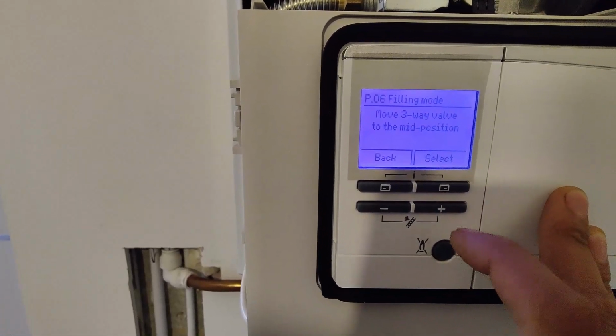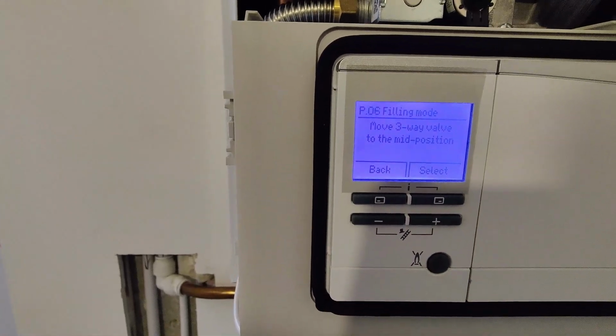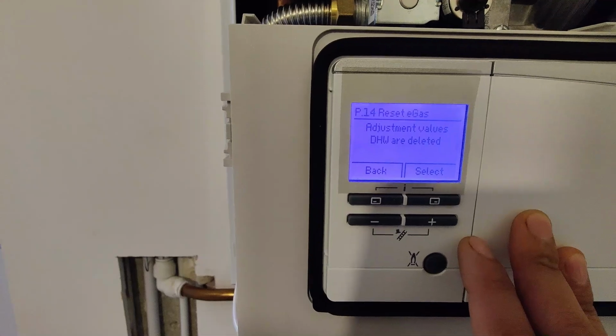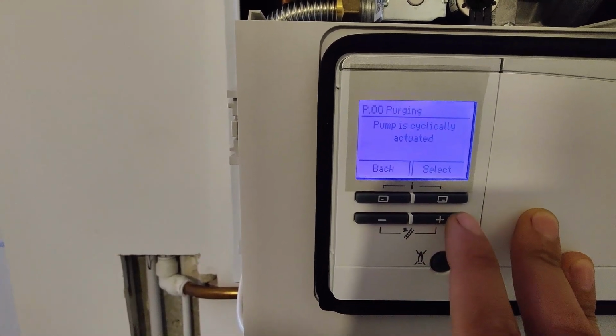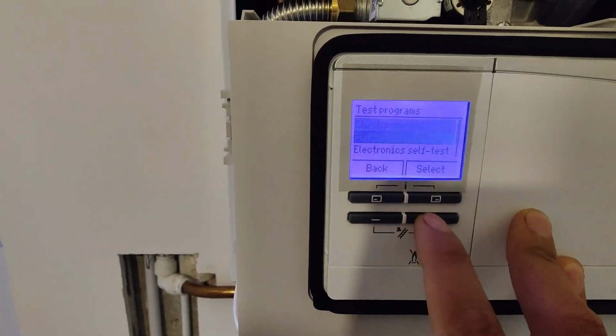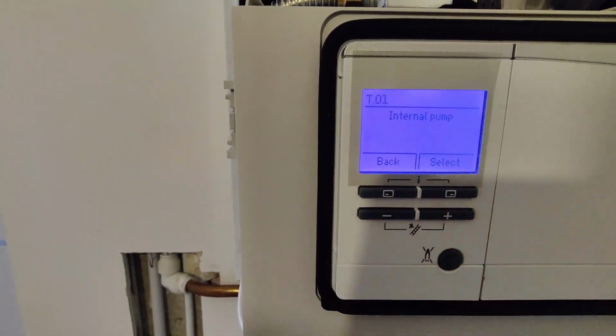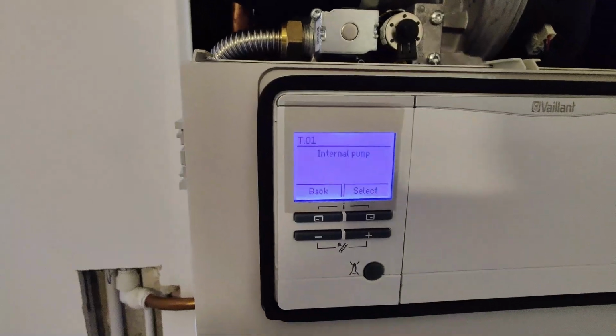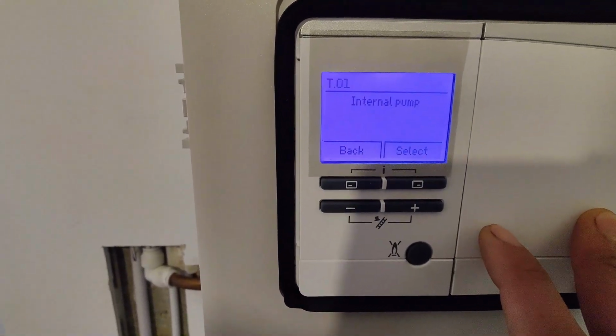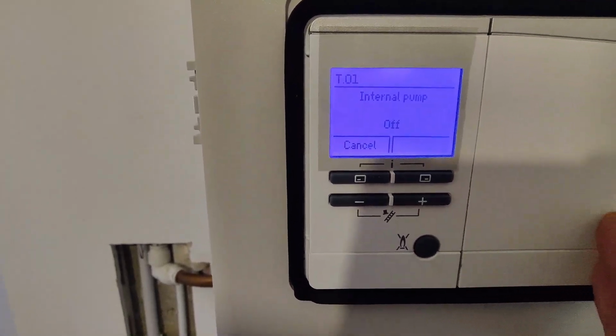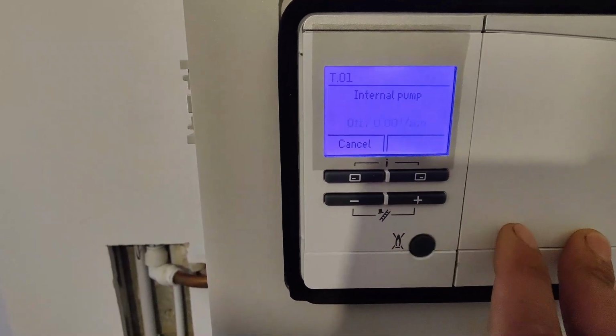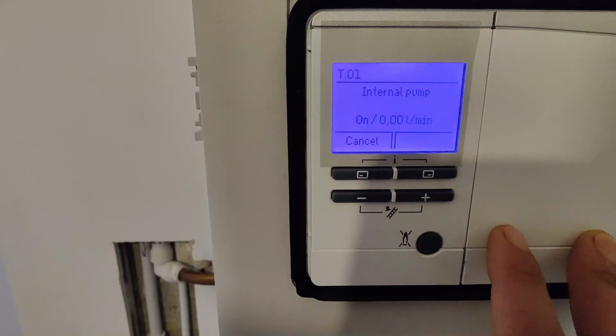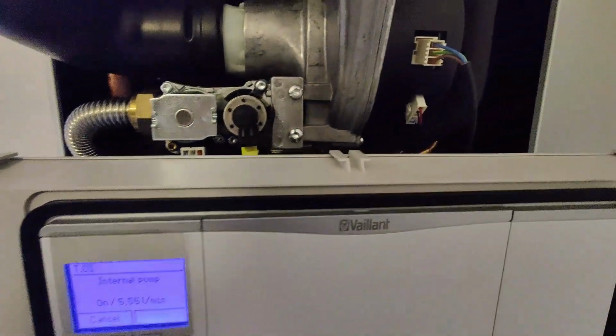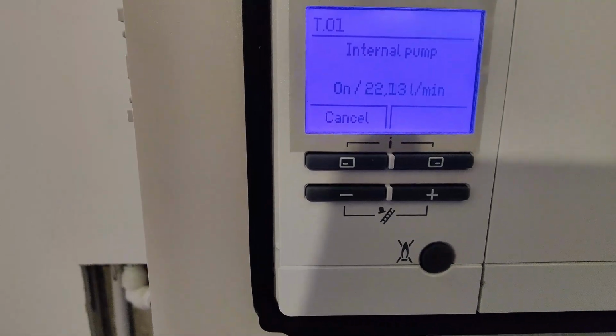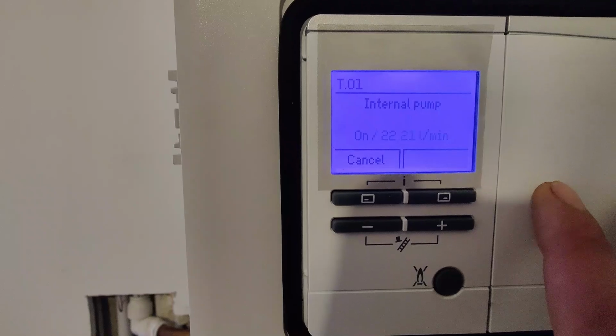P04 reset, so adjustment valves, so central heating. And then filling mode, when you fill the system, that moves the diverter valve into mid position, as it says. It's got all sorts of settings on this one, and then it comes back to P00. In the function menu, again, you can test different components by just activating them from here. As you can see, T01 says internal pump on it, so we can select that. Currently it's off, there's no demand, and it's showing us how many litres per minute is pumping, which is obviously 0. We can turn it on from here, and I'm not sure whether you can hear, but the pump now is on, and the screen confirms how many litres a minute is pumping. So the pump came on.